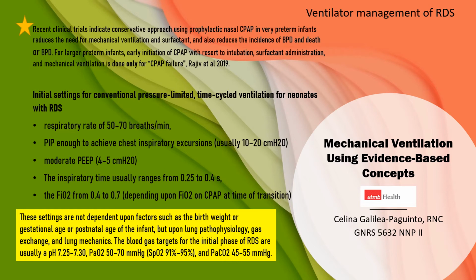The initial settings for conventional pressure-limited or time-cycled ventilation for neonates are the following. We use respiratory rate of 50 to 70 breaths per minute with PIP enough to achieve chest inspiratory excursions, usually 10 to 20 cm of water. We use moderate PEEP of 4 to 5 cm of water. The inspiratory time usually ranges from 0.25 to 0.4 seconds, with the FiO2 from 0.4 to 0.7 depending upon the FiO2 on the CPAP at the time of transition.